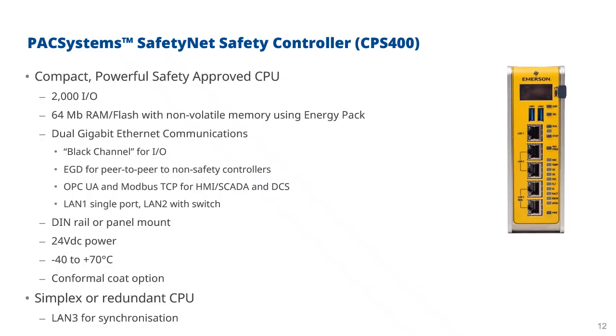Now we've got multiple gigabit Ethernet communications. We've got dual gigabit Ethernet on ports LAN 1 and LAN 2. And with those, we can implement the black channel for our I/O communications. So the black channel is part of the safety application. And what black channel means is you can't see inside it. It's black. We as Emerson have taken control of what that I/O is doing, and we certify it for safety use. And the idea is, people say, well, what happens if the black channel goes wrong? Well, then if the black channel communications fails, then the I/O would go to its default state, typically off, which would cause a trip of the plant. So it's a safe communications mechanism that is protected against spurious and incorrect messages, and we call it black channel communications. It's actually based on our Ethernet Global Data Protocol, but with additional work to make it safe, and that's where the black channel part comes in.